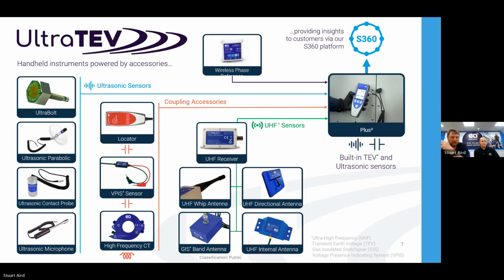So big expansion in the UHF area and taking it away from metal-clad switchgear to outdoor compounds and higher voltage assets. In the coupling devices, so looking more at the TEV type coupling and other options, we have the locator, which has been an established product for a while now. So that helps us narrow down where PD is coming from in the TEV area. But we've also brought out the VPIS sensor. So that's probably been out for a couple of years now, but we've really seen a big adoption this year. And that's allowing us to very quickly look panel by panel into the VPIS sockets on the front of the switchgear, and allows you to narrow down PD to the phase with a very simple, quick, repeatable measurement. So it's literally as simple as the two connections, hit record, move on. So that's seen some wide adoption because of that.